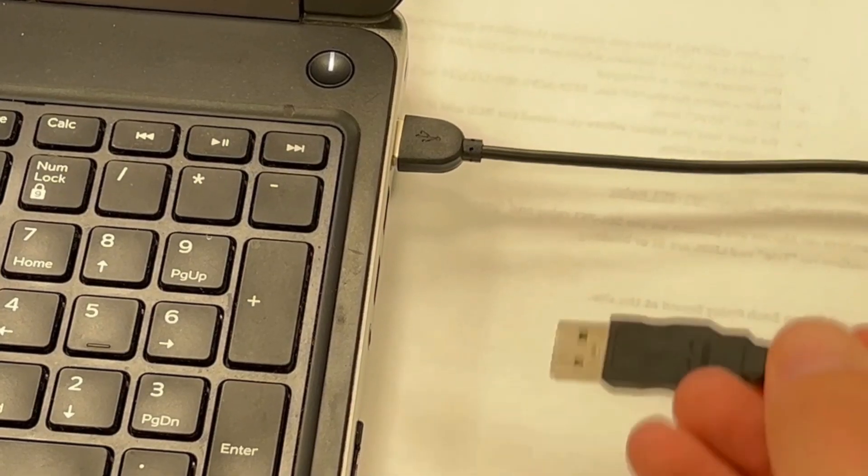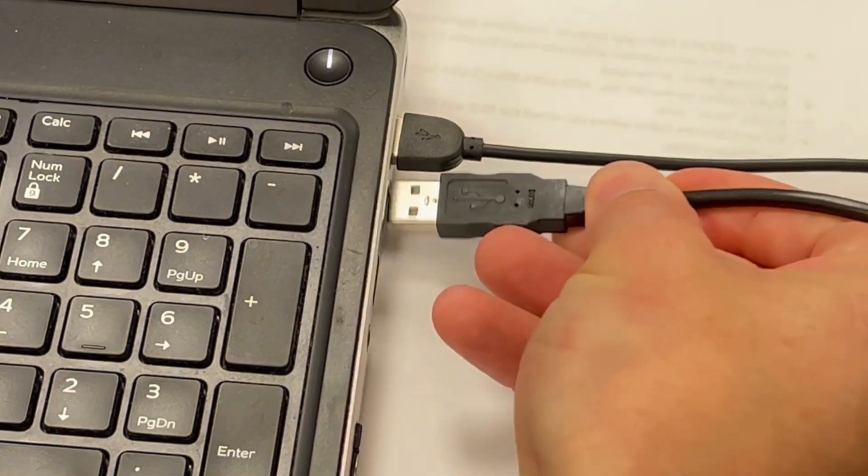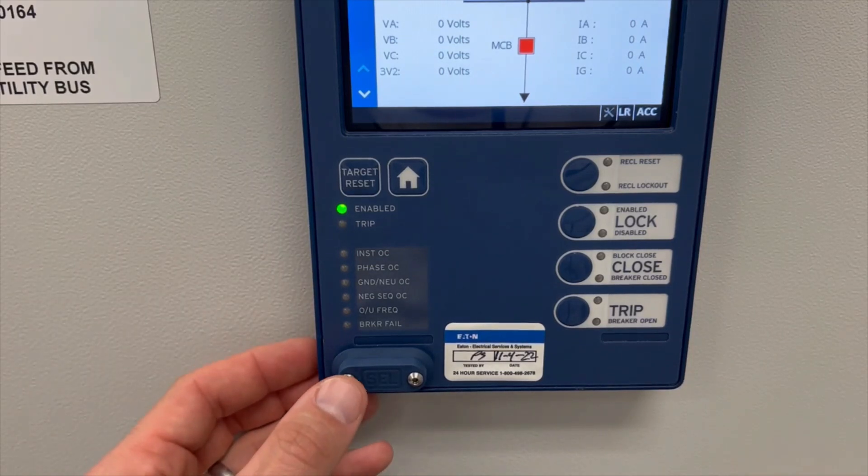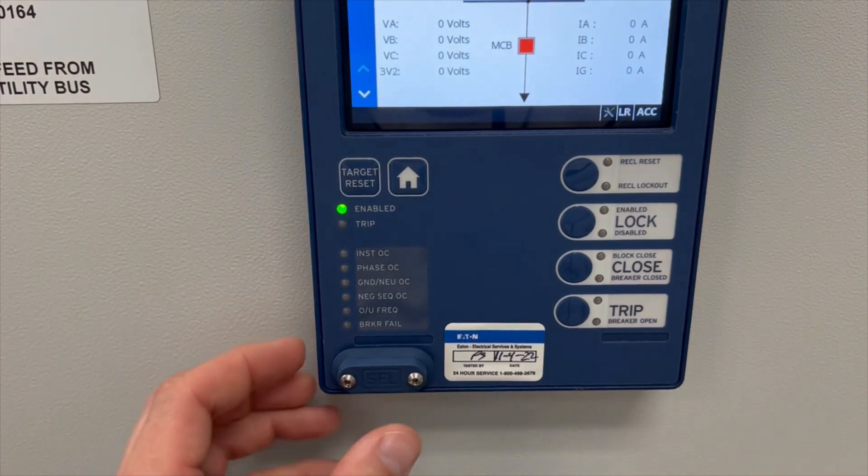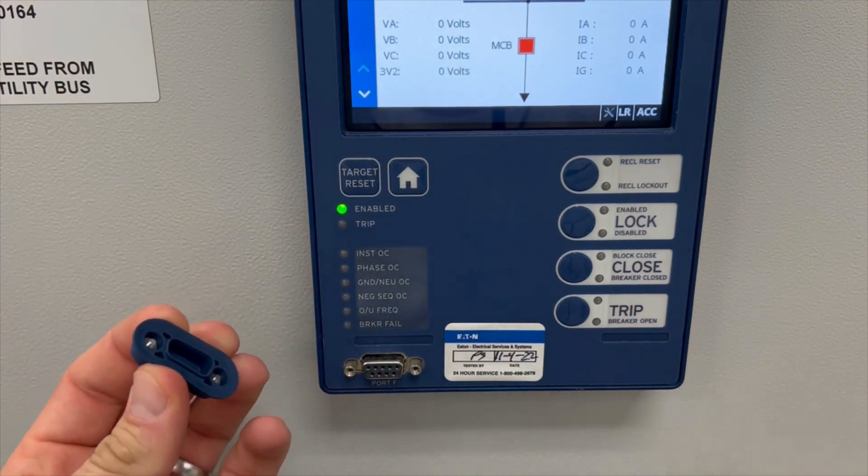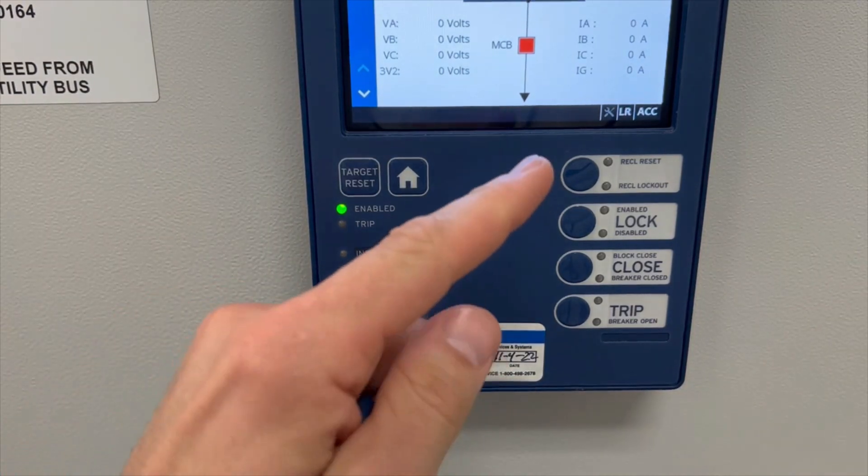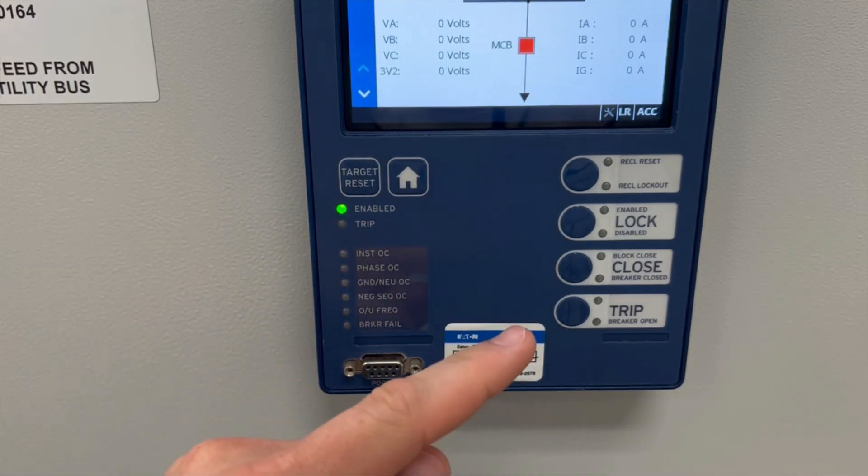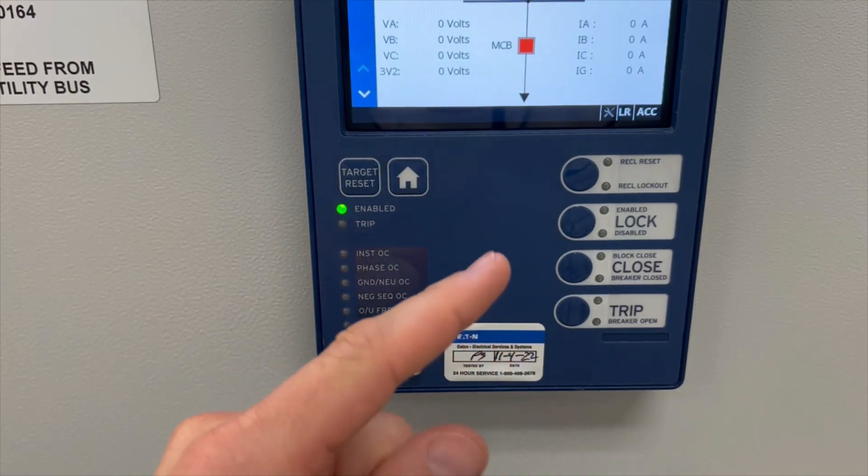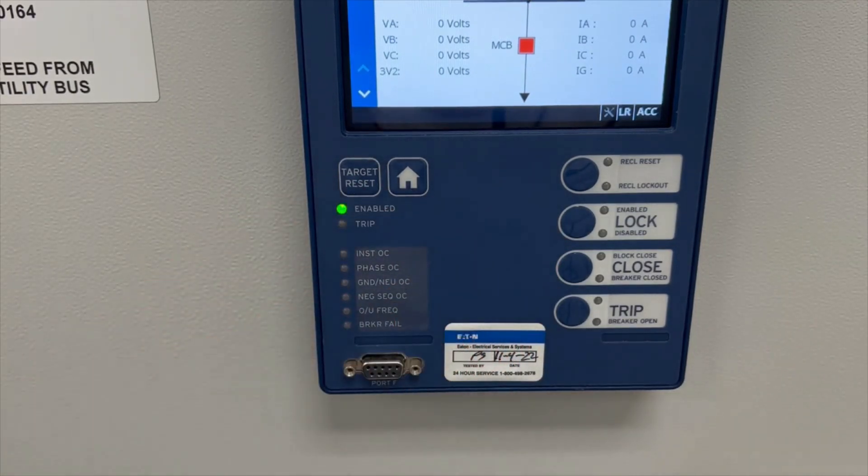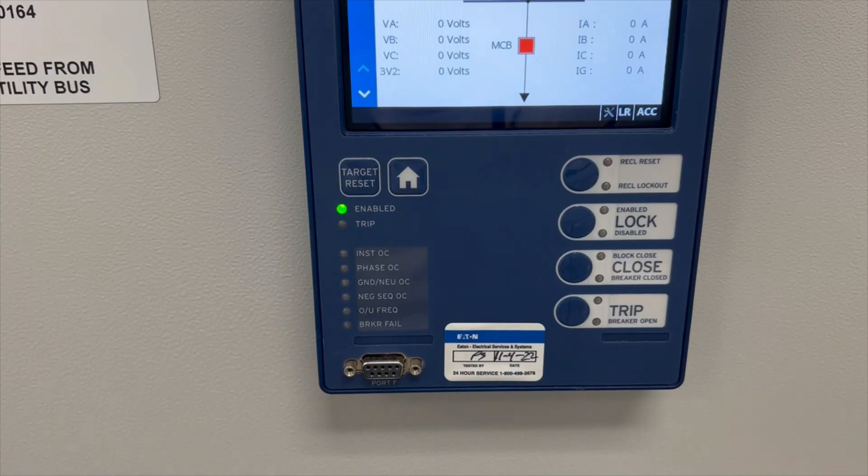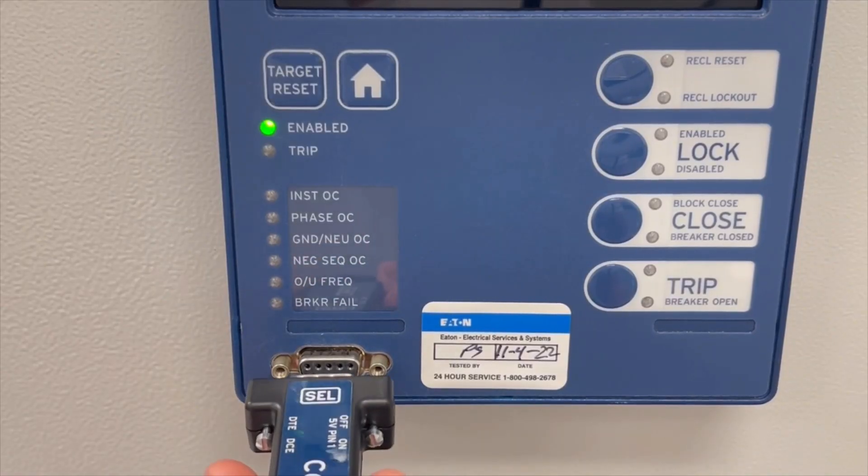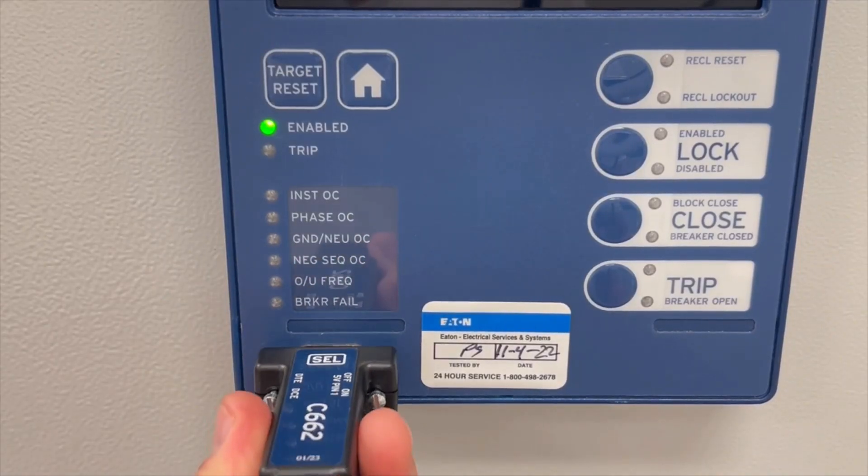Connect the USB end of the serial cable to the laptop. To access the serial port, remove the two flat head screws and remove the cover. Be careful not to bump into the lock, close, or trip as this may activate the device that this relay is protecting. Connect the serial cable to port F on the relay.